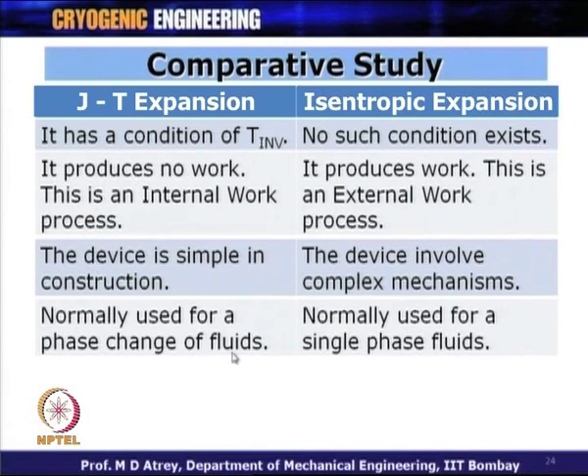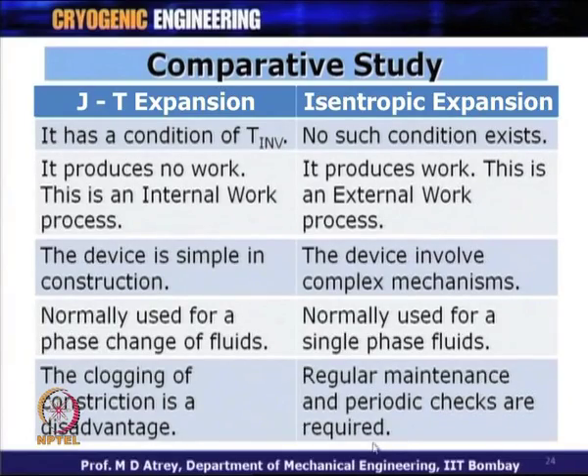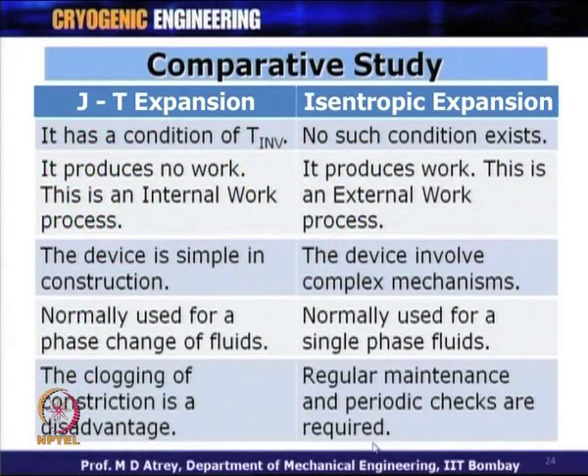JT expansion is normally used for phase change of fluids — working with real gas — so we prefer phase change during expansion. Isentropic expansion should work with single-phase fluid, as two-phase fluid is not acceptable to turbo expanders or reciprocating expanders. JT valve constriction can clog with dust or particles, while isentropic devices require regular maintenance, periodic checks, and lubrication.